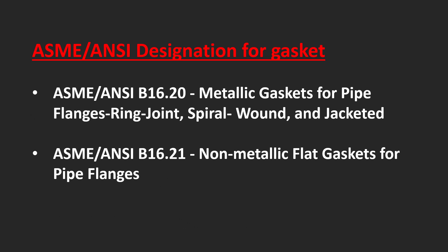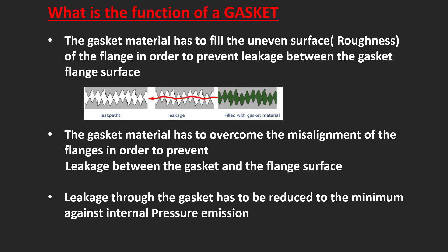ANSI designations for gaskets: ANSI B16.20 covers Metallic Gaskets for pipe flanges, including Ring Joint, Spiral Wound, and Jacketed types. ANSI B16.21 covers Non-Metallic Flat Gaskets for pipe flanges. The roughness of the flange must be considered in order to prevent leakage between the gasket and the flange surface.